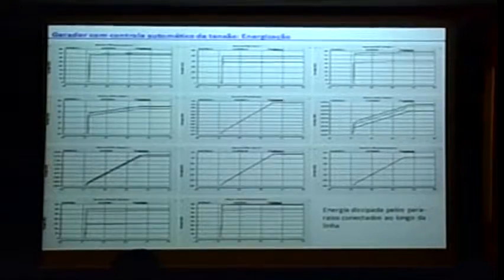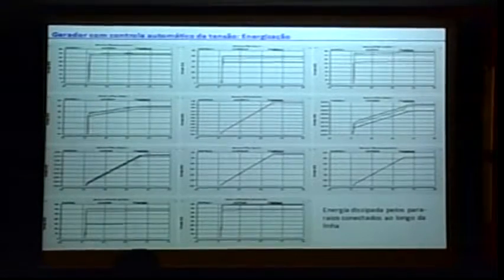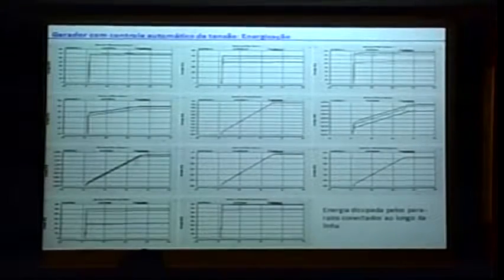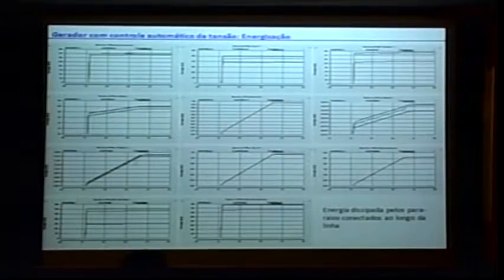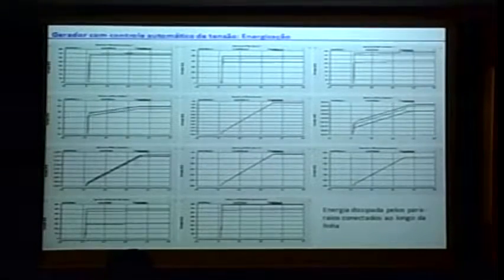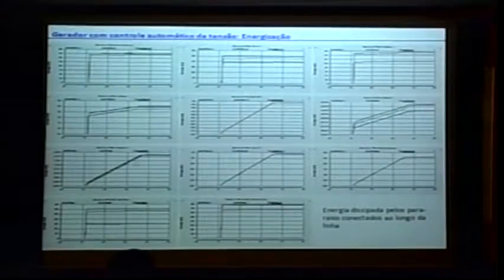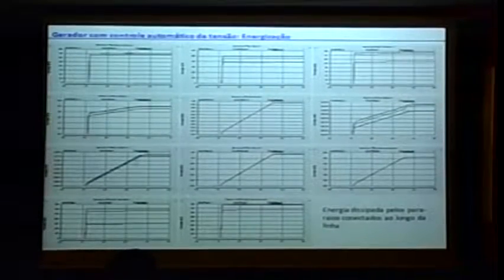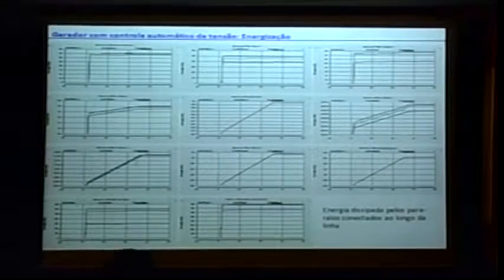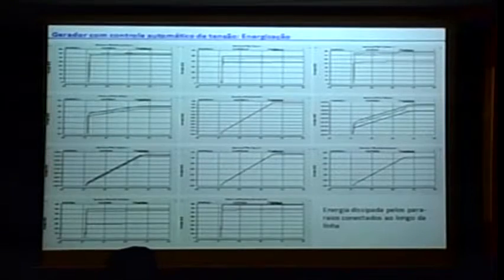Here, during the energization, would be the energy dissipated in the surge arrestors during the no fault energization test. So practically all surge arrestors dissipated a quantity of energy, but all here in the order of kilojoules, a small quantity of energy in the dissipation. There is a gap in Imperatriz. In this case of energization, the gap has never actuated.